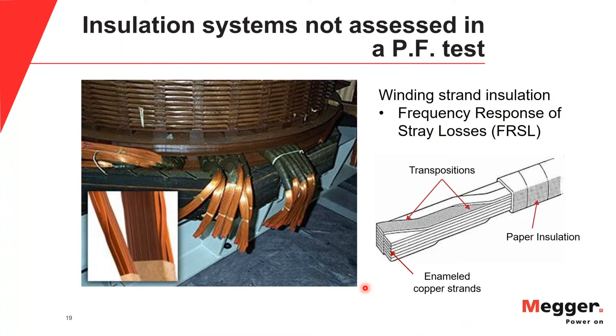Finally, we have strand insulation. If the paper insulation of a winding conductor were cut back, it would be seen to be composed of several individually insulated strands. Furthermore, the strands are transposed — no one strand occupies the same position within the entire length of the conductor — and this is to control losses. If two or more strands short together, this effectively reverses the efforts taken to control these losses. The only test in which this type of problem is relatively easy to see is frequency response to stray losses, which was introduced in the 1960s.